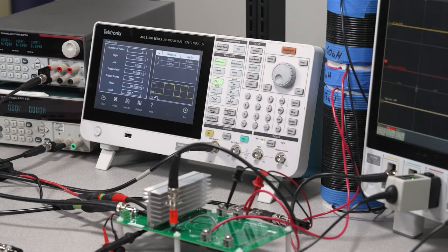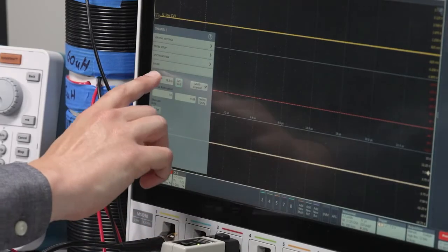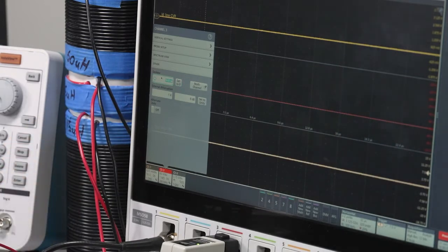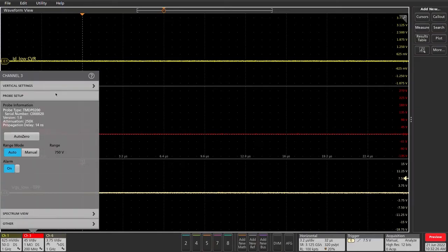I used a splitter and pulses from the AFG 31000 signal source to de-skew the probes and the CVR cable. With the probes de-skewed and warmed up, power to the DUT turned off, I'll run a quick auto zero. This will remove any imbalance that will affect switching loss measurements.